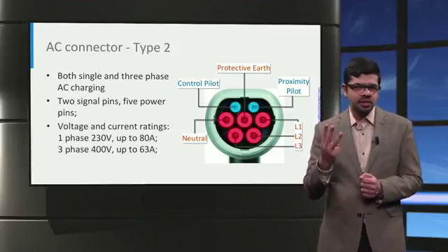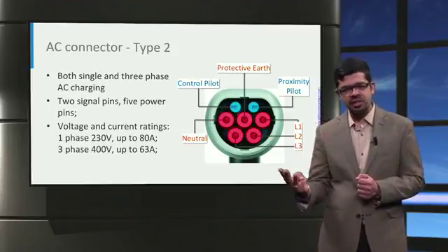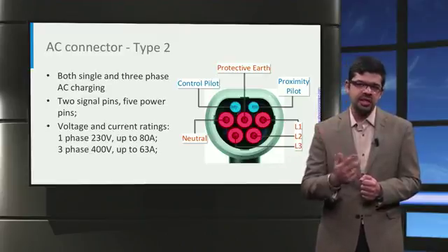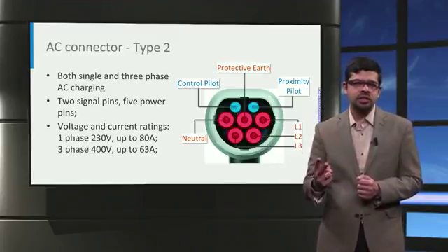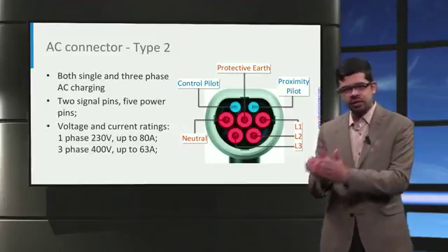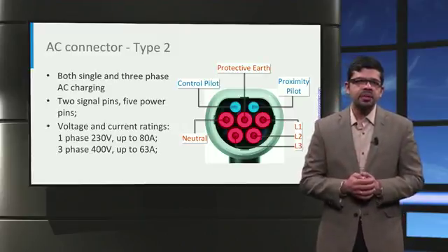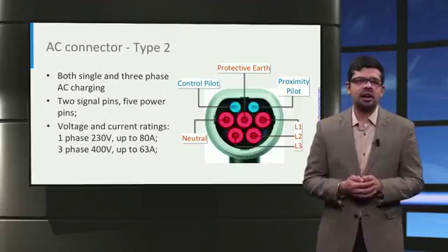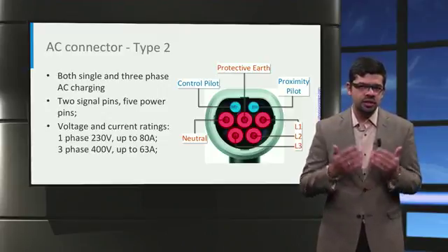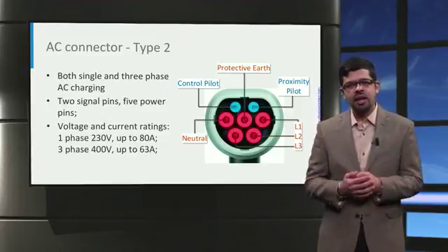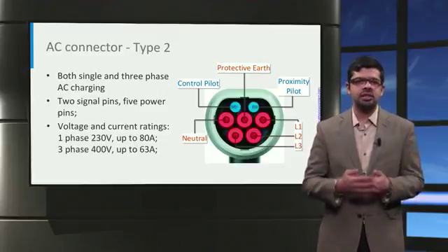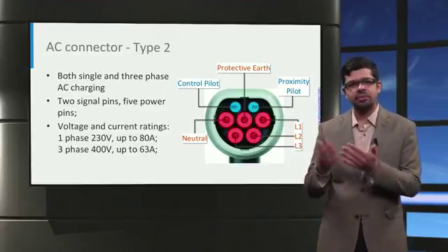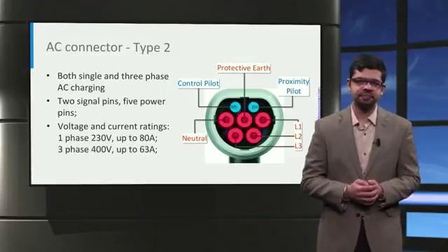There are 3 pins used for the 3-phase AC connection: phase A, phase B and phase C, and then 2 pins used for the neutral and the protective earth. The maximum voltage and current ratings are: single phase 230 volts up to 80 amperes, and in case of 3-phase, the voltage is 400 volts with current up to 63 amperes.